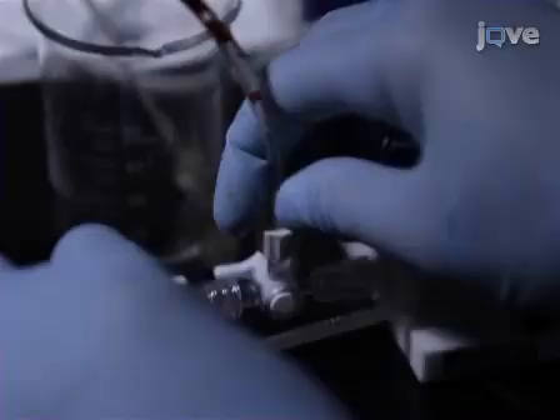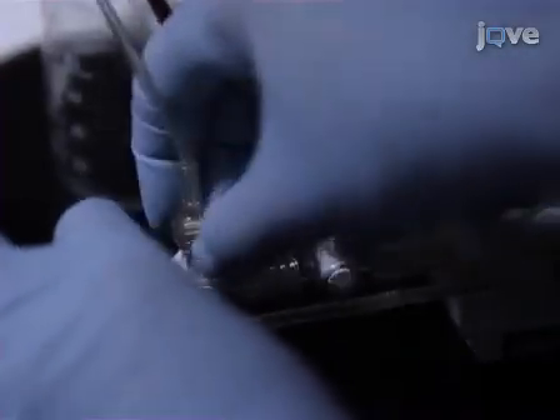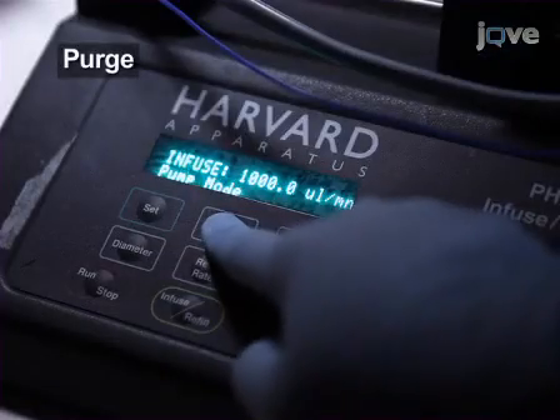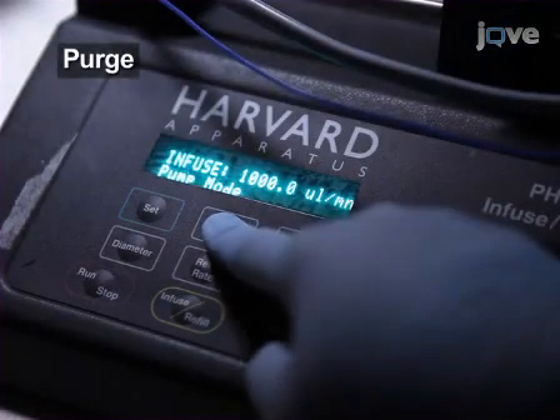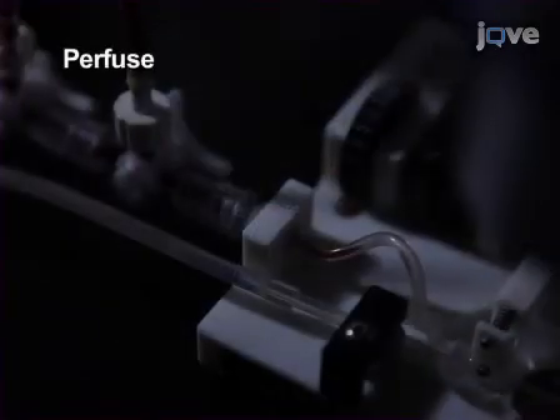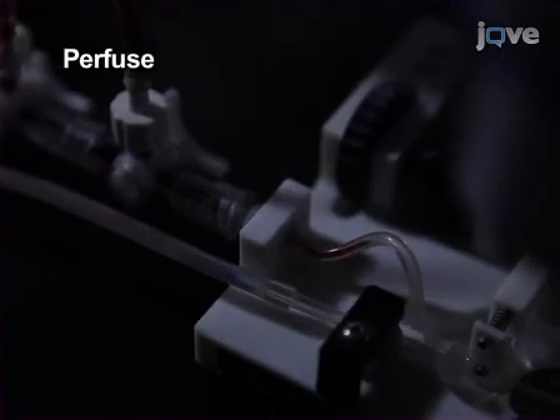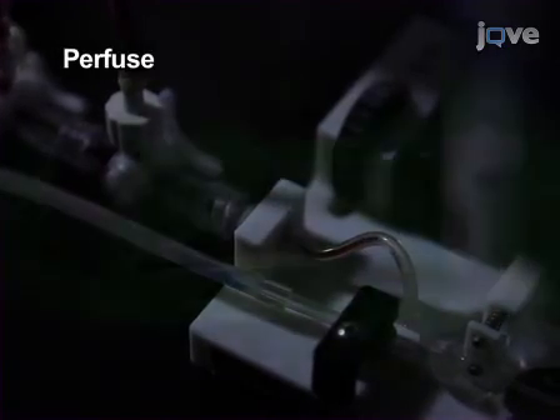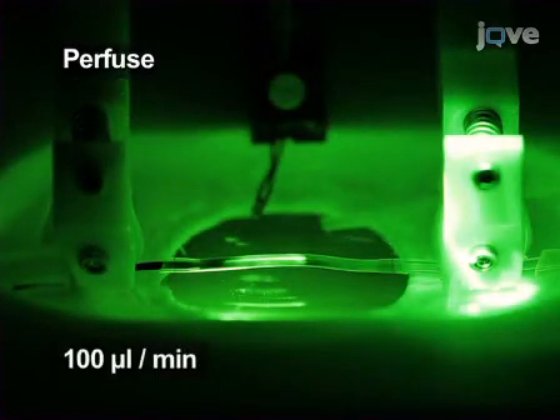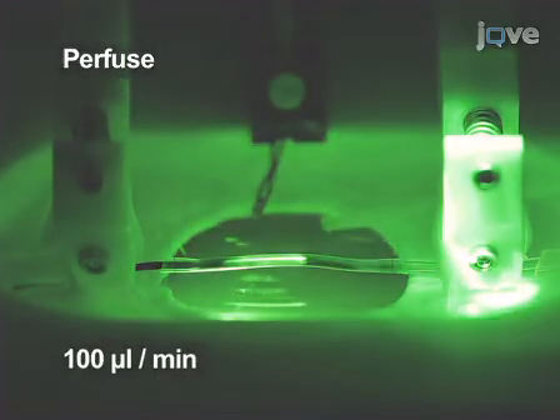Close off the P1 transducer to the chamber and connect the syringe and waste tubing. Purge the blood at 1000 microliters per minute through the waste tubing to remove any air bubbles. Open P1 to the chamber. The pressure servo will adjust automatically to maintain the desired pressure. Perfuse the blood at 100 microliters per minute.